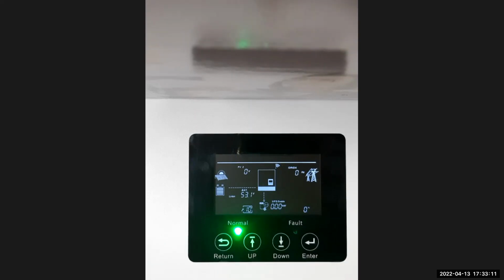So number 10. Now number 10 is basically you're telling this inverter with which settings it must work. If you have a battery that communicates, you're always working on SOC. That means state of charge, percentage wise. A battery that's communicating, you always run on SOC. A battery that can't communicate, you run on volts. Then all the parameters that you set in voltage will follow. If you put it back to SOC, all the parameters that it's following at this moment will be on the ones that you've added percentage wise.